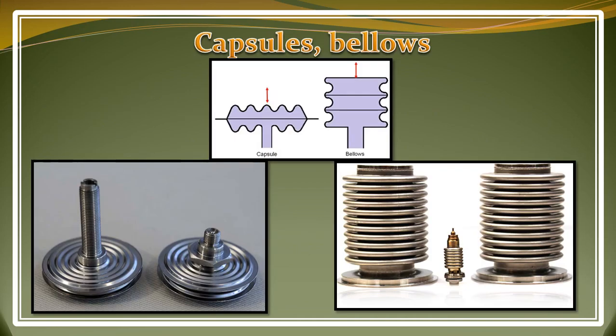When we move to capsule or bellows, you can understand from the figure. Here on the left side is a capsule, and this right side is a bellow. When we apply a pressure on a diaphragm, it deflects, and by this we can measure the pressure. In a capsule, two diaphragms are merged into one, so we can amplify the deflection. Here you can see two corrugated diaphragms, one upper and one lower, both connected and joined. When we apply pressure, as the corrugated diaphragm increases the area, the output will be much higher. So we can make capsules and bellows, and amplify the output of pressure.